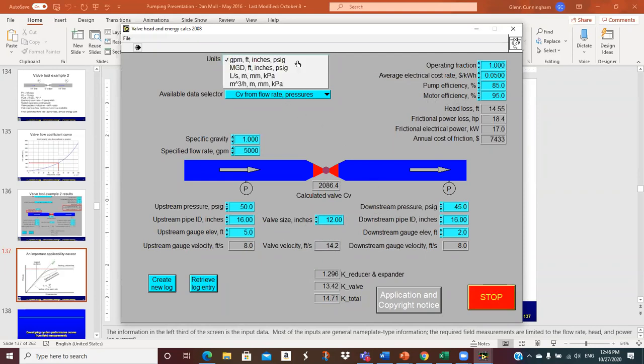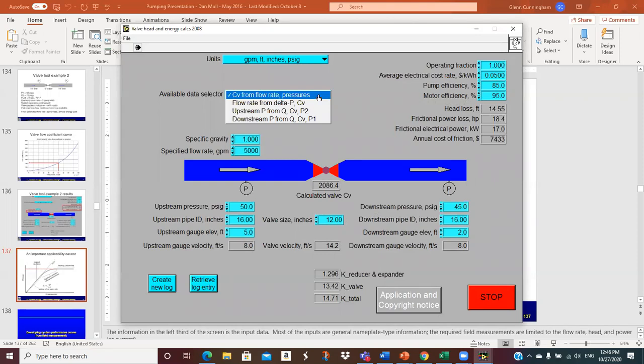So again, like I said, these are all of the different units. Wastewater folks pump a lot of water, so it's like MGD, millions of gallons per day. Feet, inches, and PSIG. You can go metric: liters per second, meters, millimeters, kPa, or you can do larger flows, meters cubed per hour, etc. So you get to pick your units. And this is the pull-down where you select which three pieces of information you know. You'll have to guess and iterate if you don't know three of them, but basically we're assuming that you know three, and whatever you can, you calculate downstream pressure. So here's a calculated downstream pressure from the other inputs. Anyway, I think that's pretty straightforward.